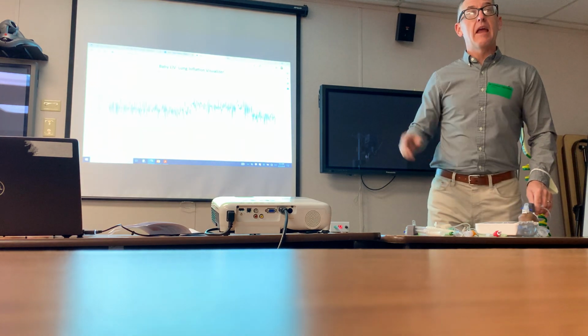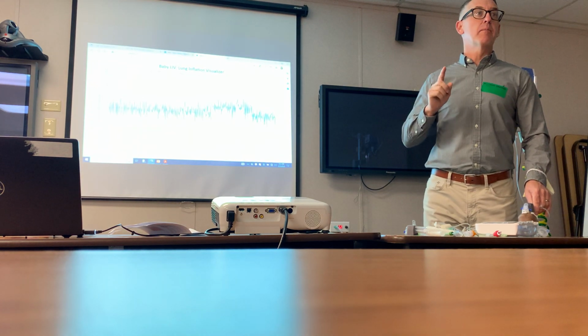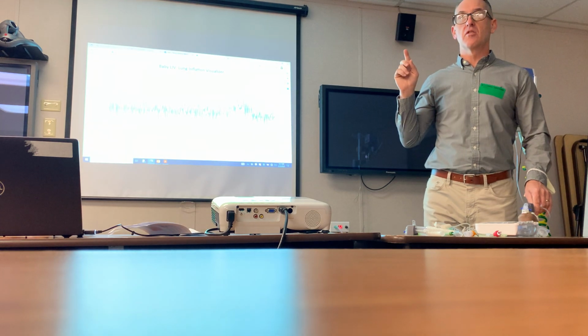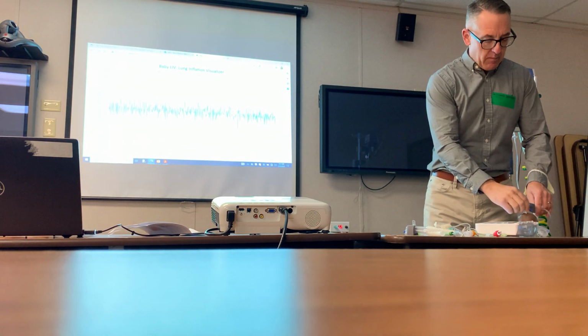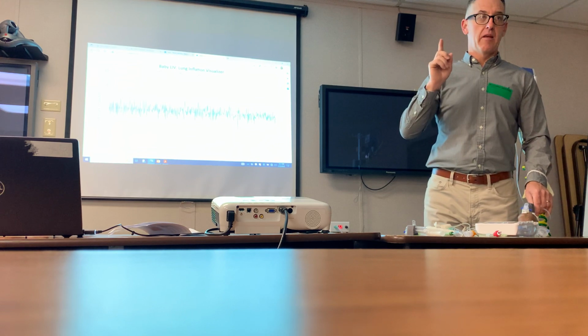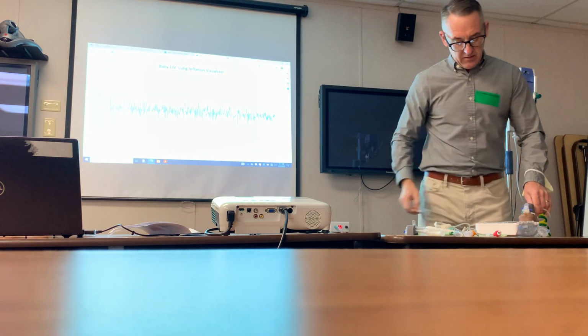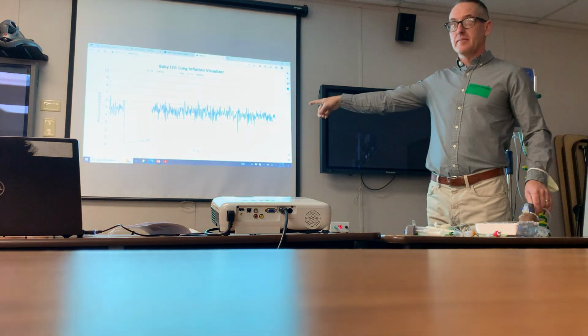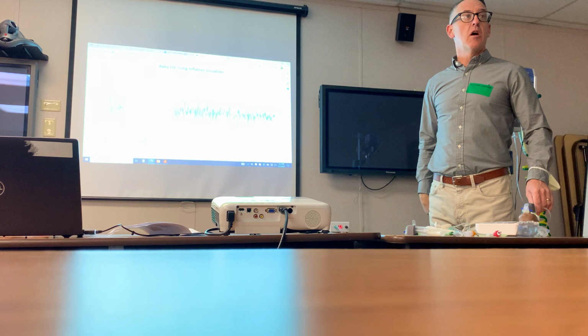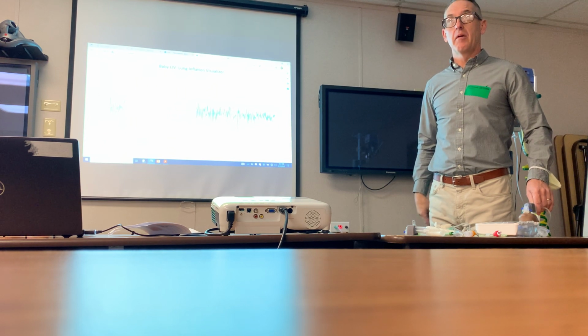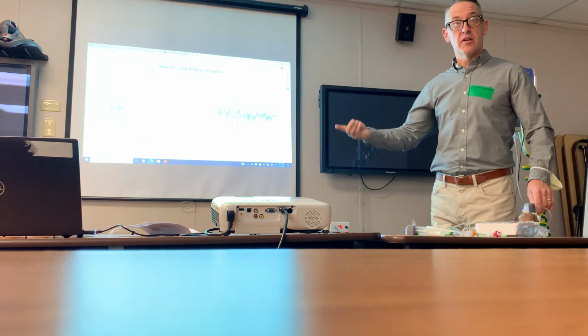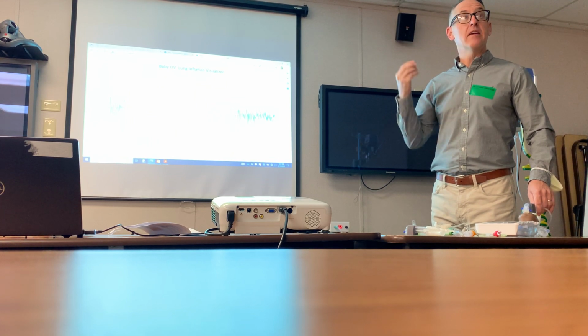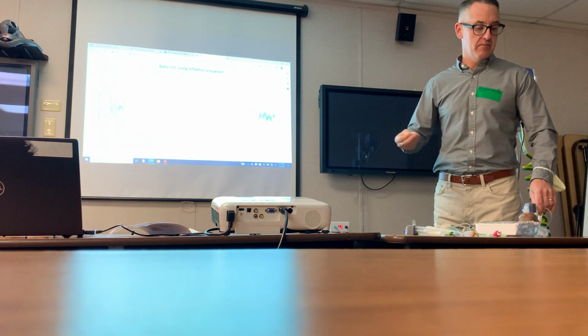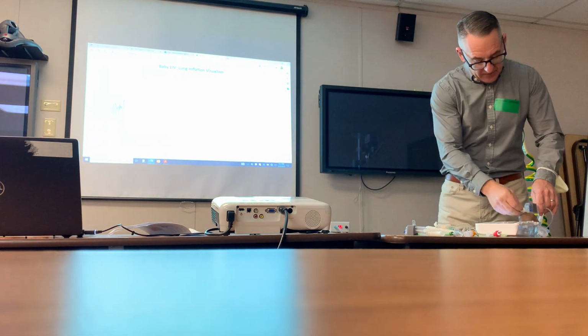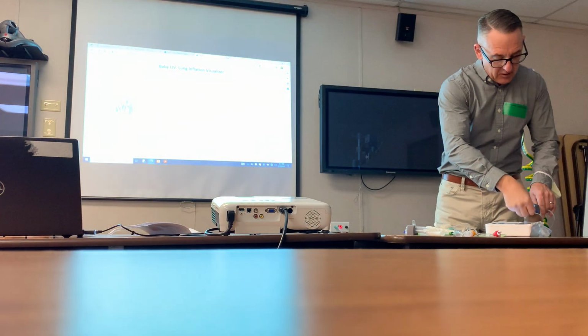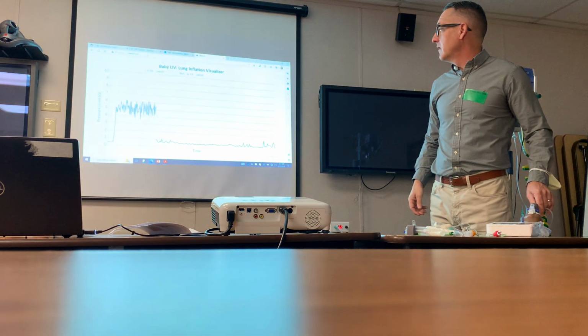When you have a mouth leak, and 30% of your kids are losing pressure through their mouth, regardless of the system that you're using in a CPAP system, the problem is you need to know that you have a mouth leak. So I'm going to take out this pacifier, because this is what happens when you have a mouth leak. Now, in this system, it's no longer bubbling because I have a leak through the mouth. So with large bore tubing and 100% occlusion of the nares, the leak lets you know by the lack of bubbling, right? This baby is down to 0.5 centimeters of water pressure. That is not nearly enough. So we're going to plug that back in, and that's what it should look like.